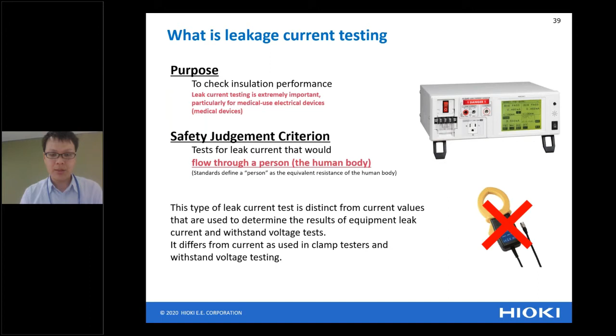As you can see, if we're talking about leakage current, someone might imagine a clamp meter or a withstand voltage tester. These kinds of instruments can also measure leakage current. But in this presentation, it has a perfectly different meaning of leakage current test. Please be careful. Anyway, it is a test for leakage current that would flow through a person, a human body.